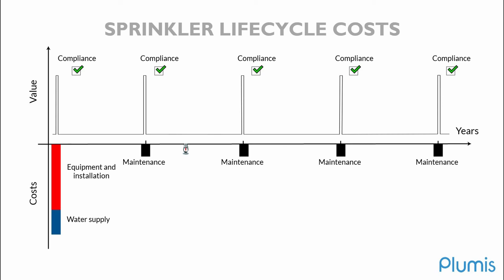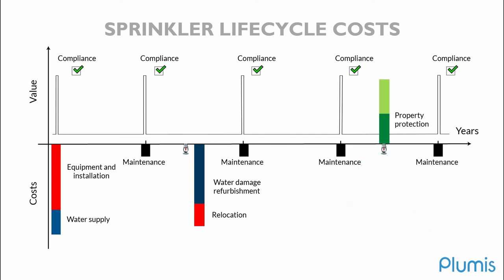Now, sprinklers don't just activate in fires. Boisterous tenant behavior can cause activations. A result of breaking that glass bulb is water damage and potentially relocation costs for any individual in that flat. Now, it's also important to not ignore that sprinklers do provide very good fire protection qualities. So if you do have a fire, you will get the proven property protection and life safety that the systems provide. But inversely, you will also have that consequential water damage and potential relocation whilst you're making that property fit to inhabit again.